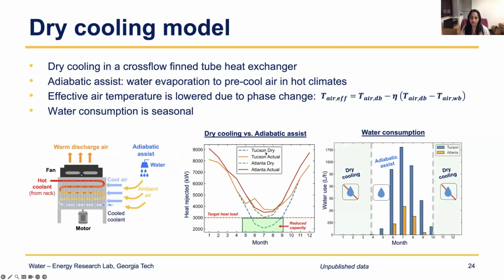This is in the US. So in a dry climate, like in Arizona, versus here in Atlanta, which is more humid, we see when you can do full dry cooling versus when you have to consume water to reject the same amount of heat. In the summer months is typically when you have to consume more water, because the ambient temperature is too high to reject heat by dry cooling alone. We can analyze this for different locations and different times of the year.